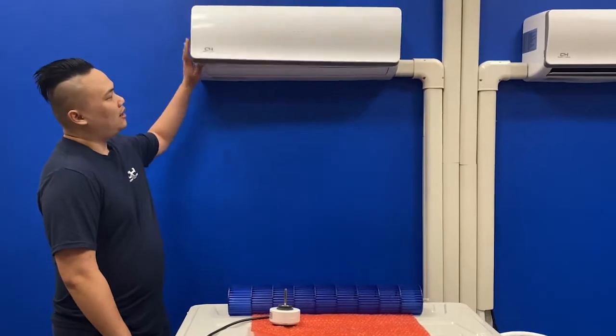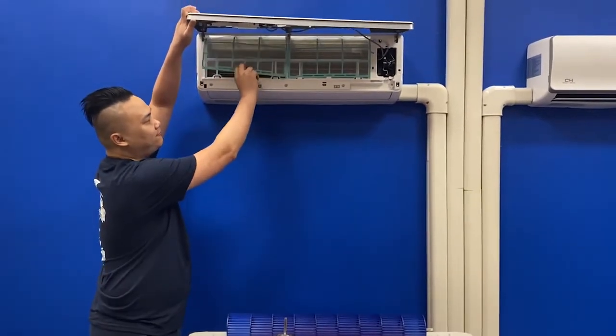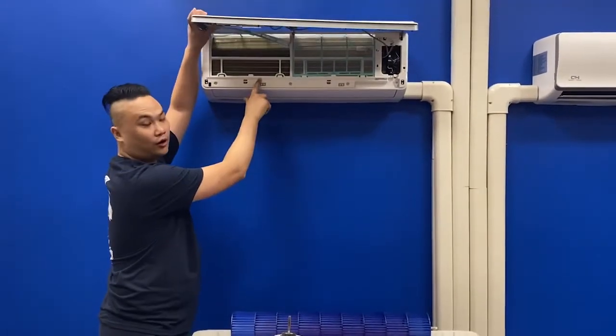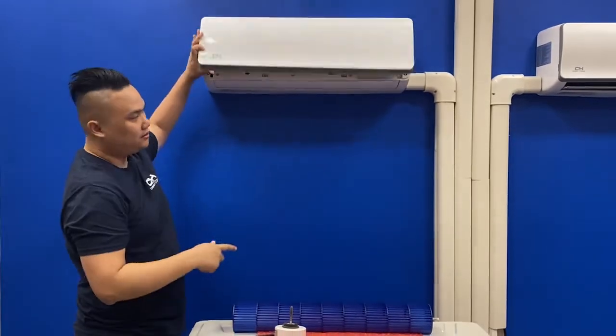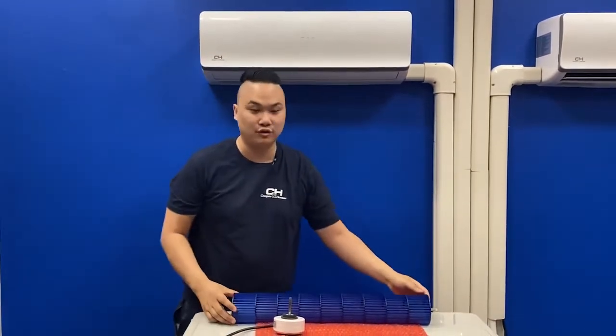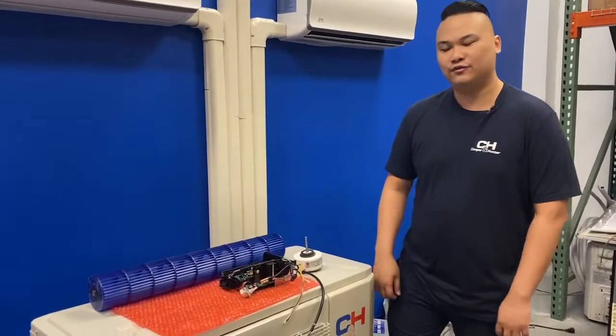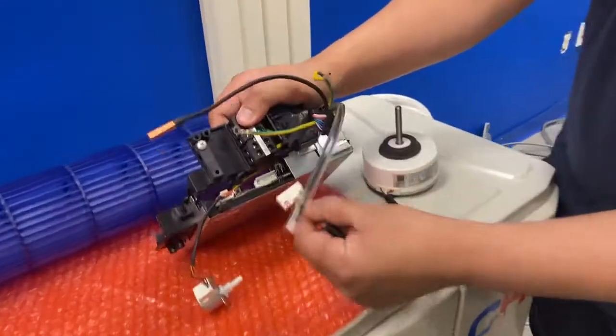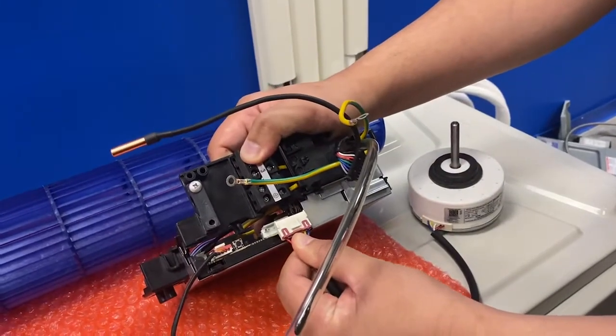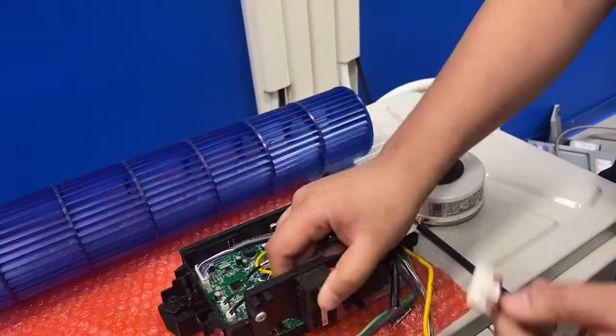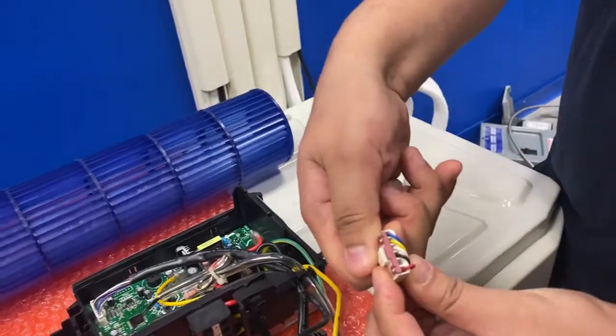First, I would verify that the filters and coils are both clean. Then, I would open up the unit and make sure the blower wheel is also clean. If that doesn't resolve the issue, I would first check to make sure that the fan motor is properly seated into the connection point. Then, I would check resistance values on the motor itself.